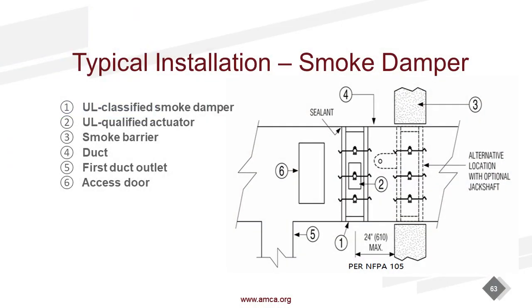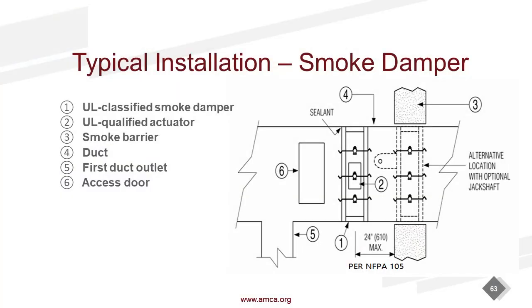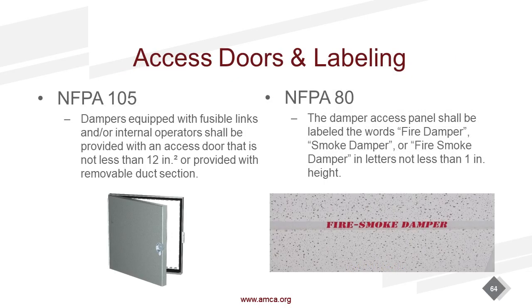Smoke dampers, the only difference between a fire smoke damper and a smoke damper or a fire damper is that the damper is not tested under fire conditions like we learned earlier, so it does not have to be in the barrier itself. It could be up to 2 feet outside of the barrier, up to 24 inches. The only exception is I cannot have a duct drop, an air inlet or outlet, between the damper and the barrier, or between the barrier and the damper. Access doors required by code. NFPA 105 will require a minimum of 12-inch square or a removable duct section.